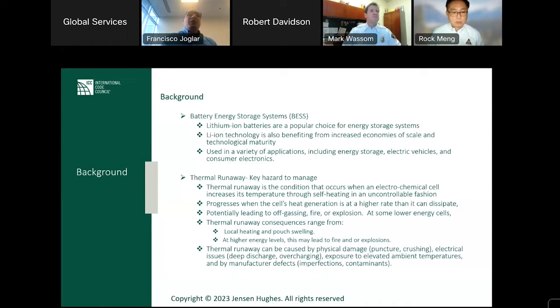So the point here is that when we look at the requirements in the standard and how to put together this documentation, the HMA, it's practical to identify what can happen before thermal runaway, and when we talk about failure modes that can lead to those, and then the actual event of thermal runaway, and then we talk about the mitigations, right? So there are failure modes that could show up before thermal runaway. They induce thermal runaway. There are mitigations for those, and then if that fails and we do end up with thermal runaway, then there is mitigation to try to control this event. So next slide, please.